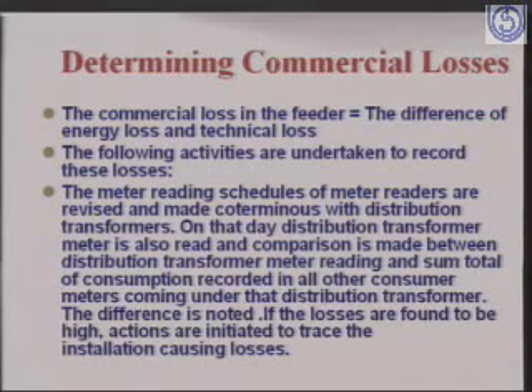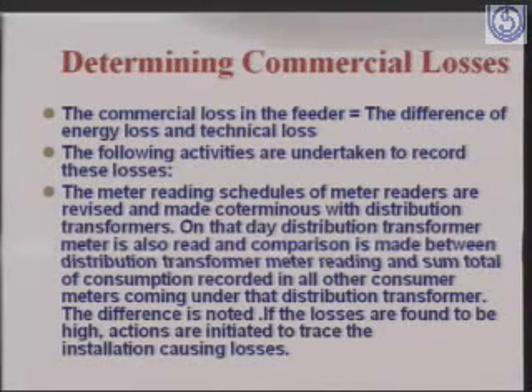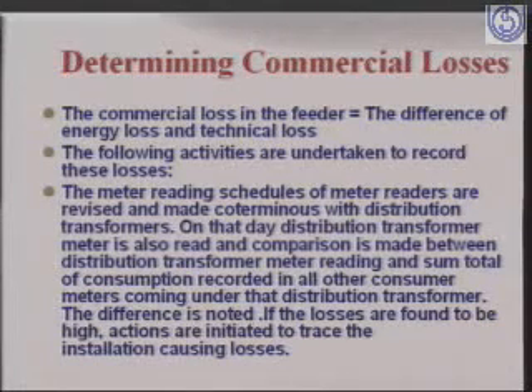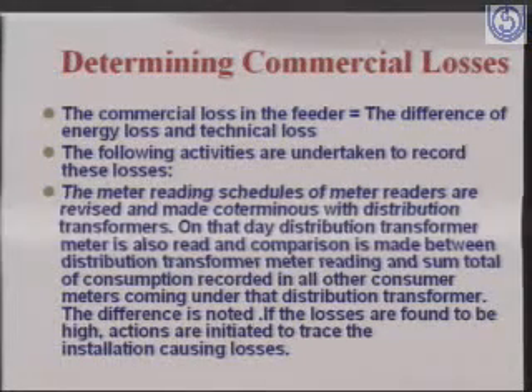This is basically the difference of energy loss and technical loss. Whatever energy has been dispatched and whatever energy has been received minus the technical loss, we have these commercial losses. So to identify commercial losses, basically we need meters, and then the meter reading schedules have to be synchronized. The meter reading schedules of meter readers are revised and made conterminous with the distribution transformers.